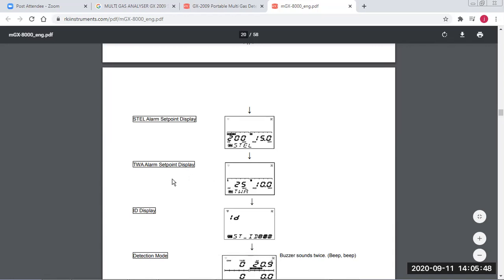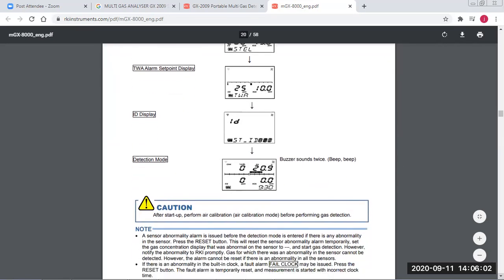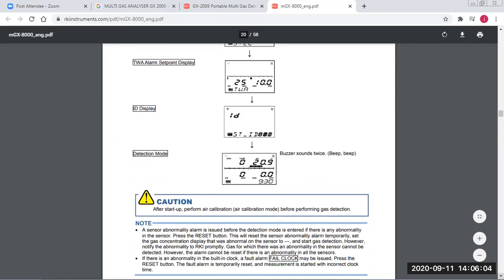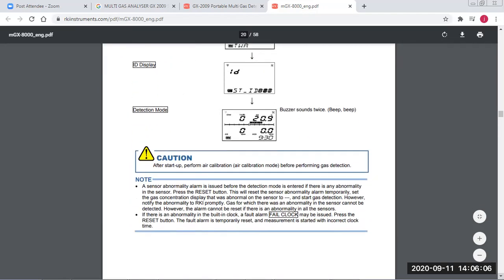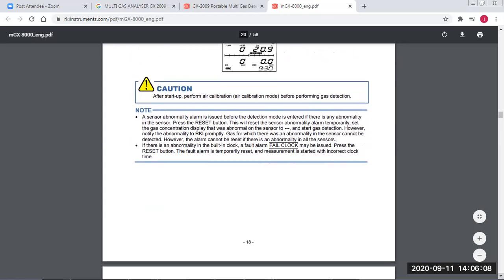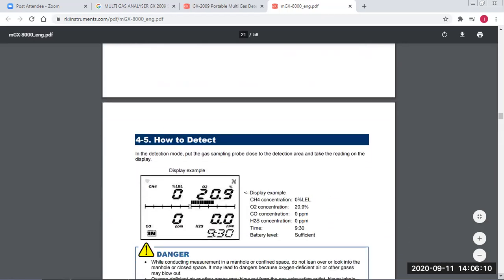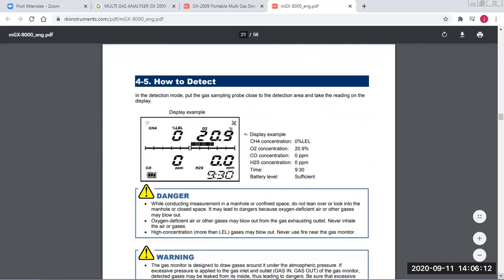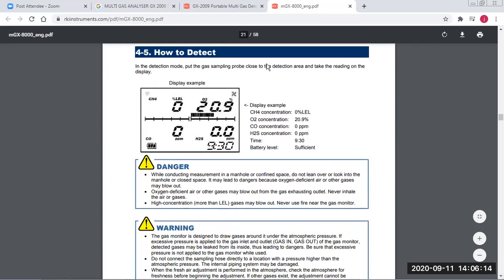Then the TWA alarm point is also there: 25 ppm for carbon monoxide and 10 ppm for H2S. That is for 8 hours a day, in a week. Then the ID of the instrument and which detection mode is there. That all is measured. So we start the instrument first in the air.